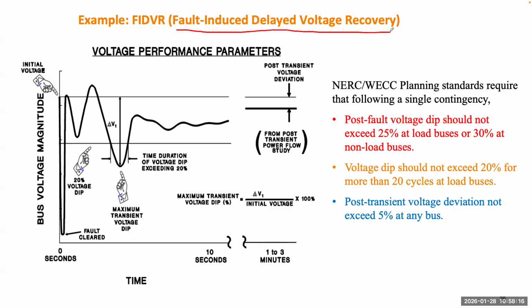This problem is because a power system may have a lot of motor load in the summertime. If the voltage becomes low, some motors will stall. So the motor will change from a resistive load to a more inductive load, and that will lower the voltage. So in Southern California, in the summertime, even just a single contingency doesn't cause instability of the system, but it will delay the voltage recovery. There was one event where one substation recovered voltage after 30 seconds or even longer. So then they designed this criteria for the planning engineer to study contingencies to make sure the voltage can be safely recovered back to the nominal value.